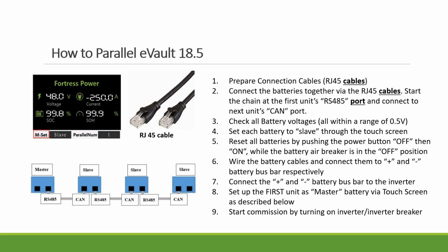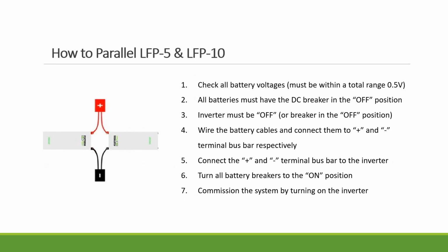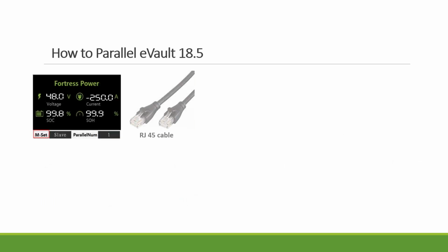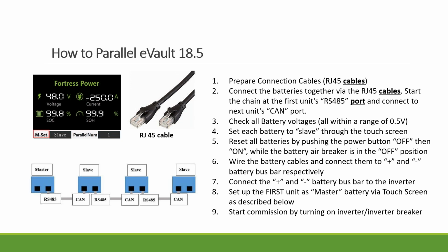That's also with the eVault, you don't have that concern when you have the communication cable connected, because it will prevent that. With the 5 and 10, that's something you will really want to pay attention to: the voltage difference between the batteries being less than 0.5 volts.